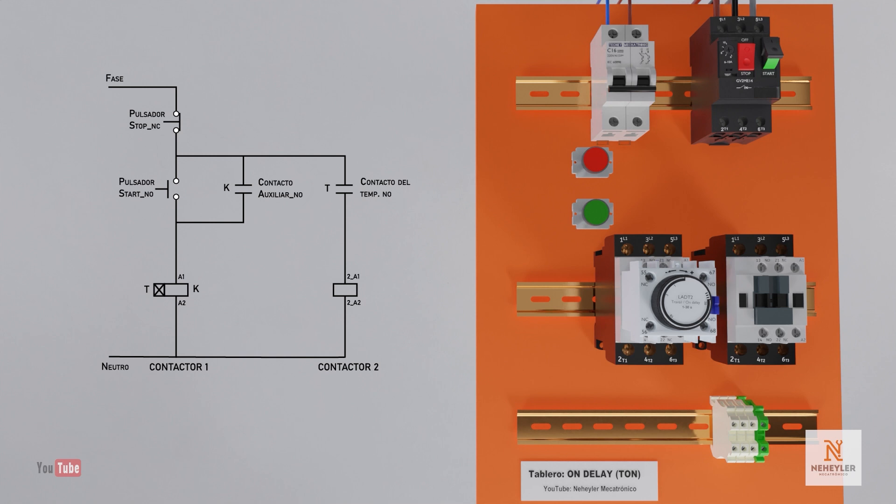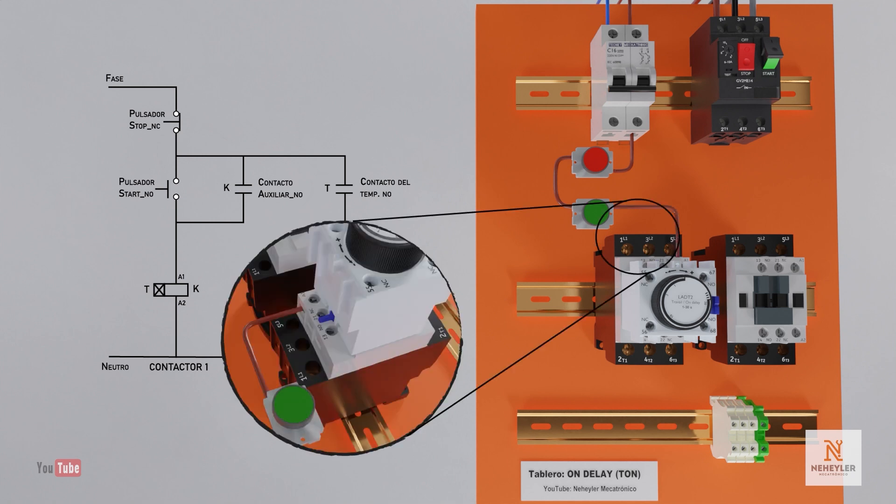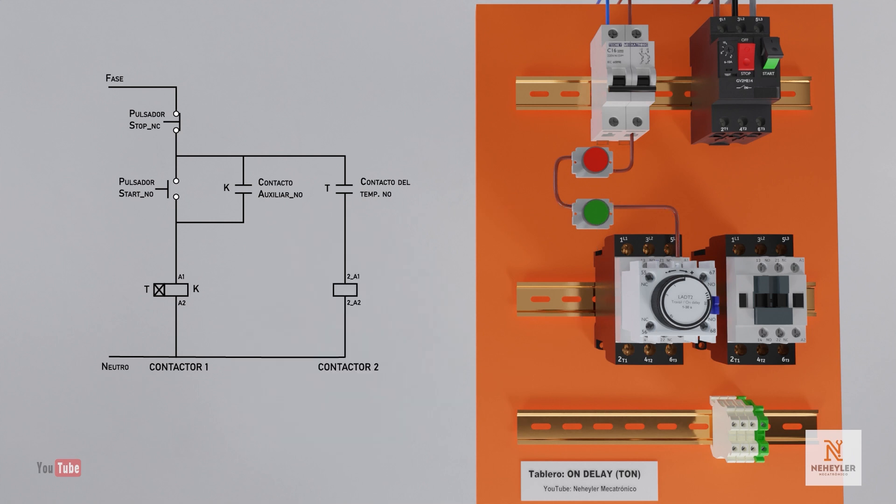From the phase, which in our case will be the brown cable, it is taken and connected to one end of the stop button. From the output at the other end it is taken and connected to the start button. And from the remaining terminal it is taken and connected to terminal A1 of the contactor coil. A cable is connected from output A2 and taken to the neutral terminal, which in our case will be the light blue cable.